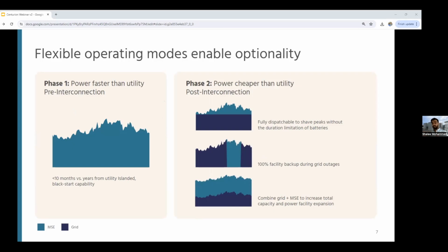And when the utility comes to the site at certain points, you don't have a stranded asset because we can then change our operating modes. We could peak shave if the rates are structured in a way that makes sense for us to peak shave, or we could play backup, only coming into the picture when there's an outage with the utility, or we can do an offset of the utility cost, still letting the utility be there. We sync into the voltage or frequency, and we just run and provide the KW for the site, which means we're taking the risk of the energy cost and the risk of the utility away from them, and providing the site power needs.